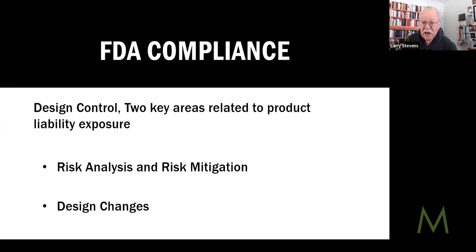It was a stop sale, and they changed the design to bump up the inner diameter of the inner lumen so it would accommodate the wider wires. Well, guess what happened? They released that. Next complaint: slow balloon deflation, because that space between the inner lumen and the outer lumen was where the fluid went into, so it was an angioplasty balloon, obviously. Oh, okay, so those were design changes that were implemented without a full assessment.